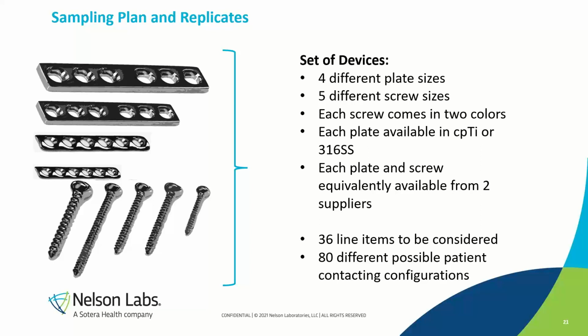Some might argue that if they were produced with the same materials and the same processes, the screws would be a more worst case cleanability, and so they might pick a representative test device from the screw grouping. But if you want to be a little more conservative, you might pick a plate as well as a screw to evaluate. And then within that group, probably just the largest surface area, so we can get better test method sensitivities. With TOC, gravimetric, THC, it tends to be the more surface area, the better the sensitivity of the test. So if you have a larger one, that's what we're going to try to push for.